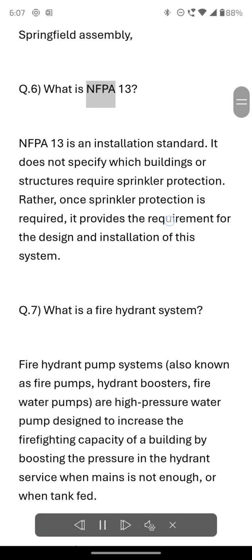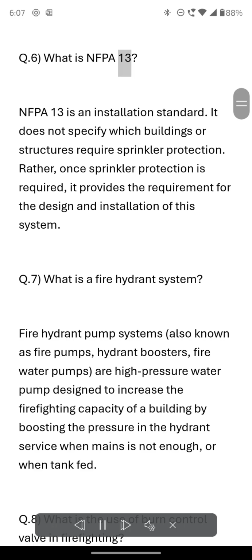Q.6. What is NFPA 13? NFPA 13 is an installation standard. It does not specify which buildings or structures require sprinkler protection. Rather, once sprinkler protection is required, it provides the requirements for the design and installation of the system.